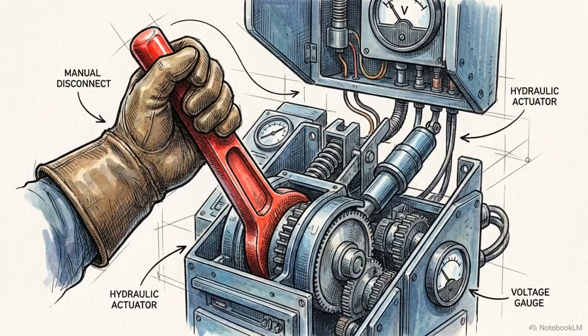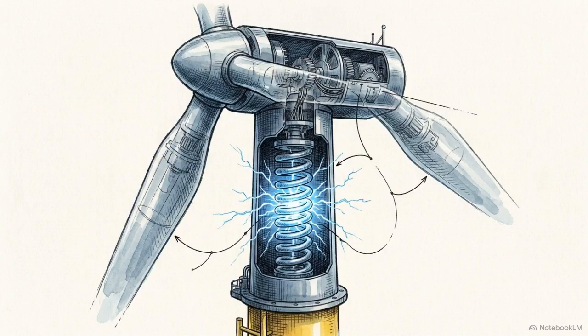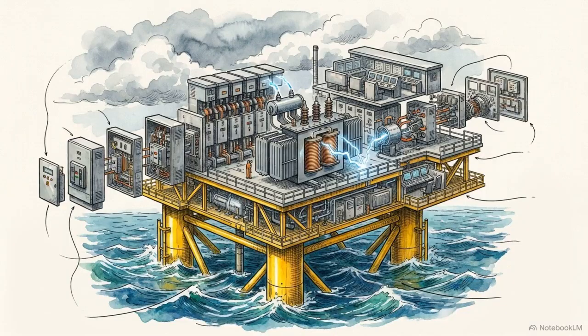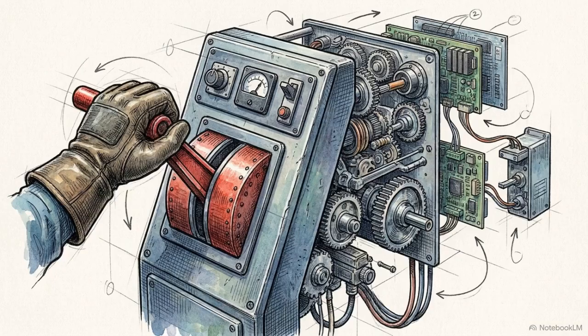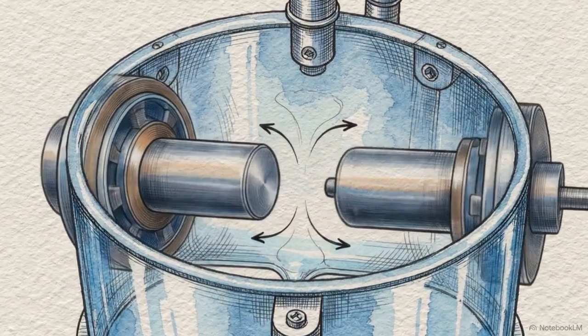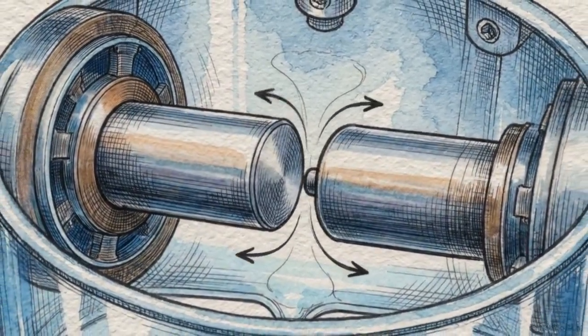The problems only start when an operator flips a switch to open or close a circuit. The infrastructure we need to bring offshore wind to land creates a tightly coiled spring of electrical tension, just waiting for a trigger. That trigger is usually pulled inside the offshore substation, which acts as the mechanical control point for the entire grid. To route power or clear faults, operators use a device called a vacuum circuit breaker.